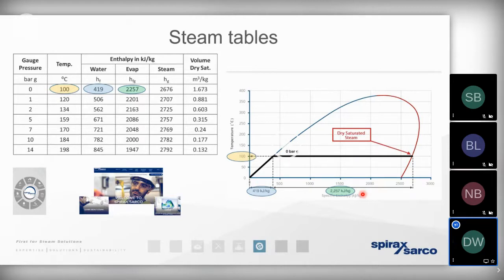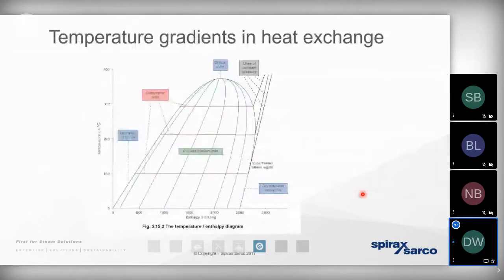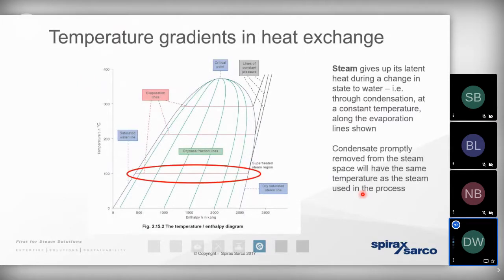So it's for that reason that everything we do with regard to steam generation and steam distribution design should be with the aim of keeping the steam as dry as we possibly can. When steam's being used to heat a process, we need to remember that it's the enthalpy of evaporation, the latent heat energy, that we add to a process, to that boiling water. That's the energy that passes from the primary side of the heat exchanger to the secondary side. We can only use this latent heat, this enthalpy of evaporation, and that's about 75% of the total heat energy present within the steam itself.